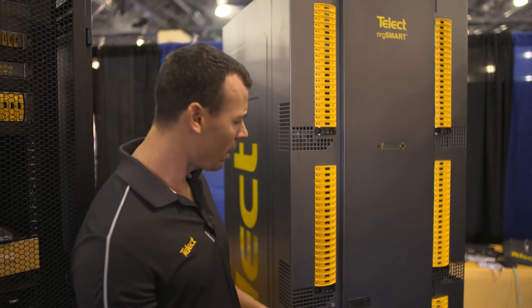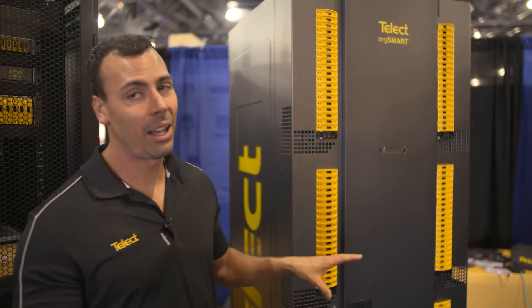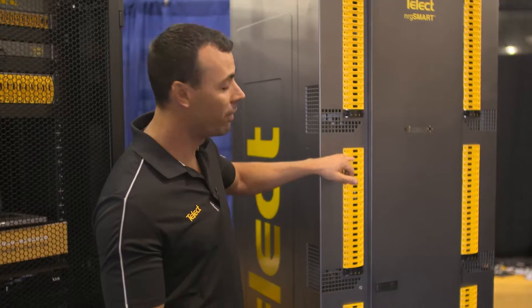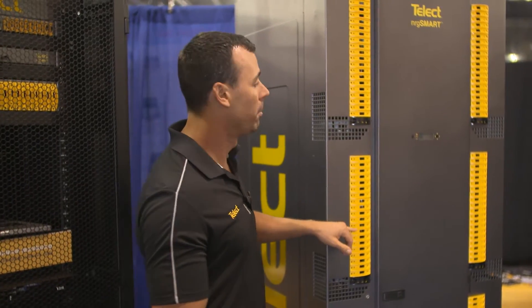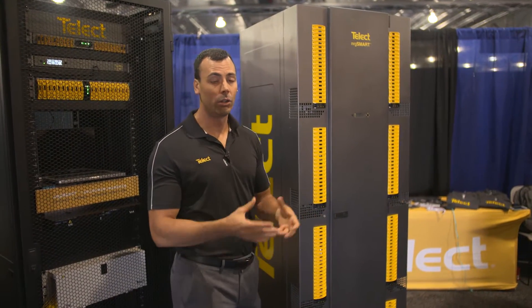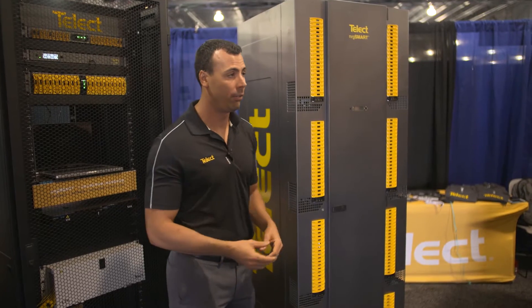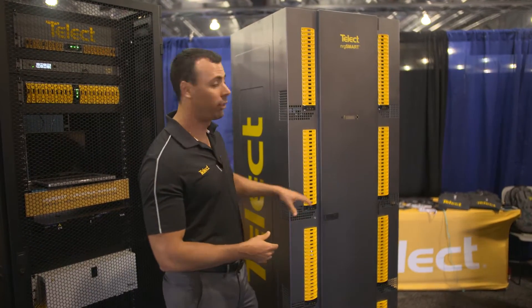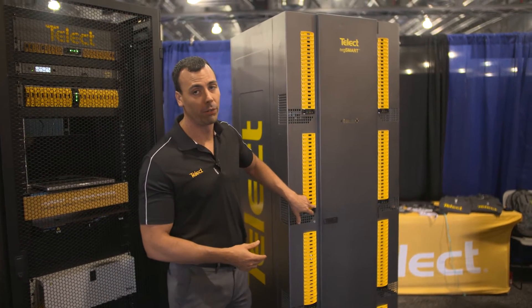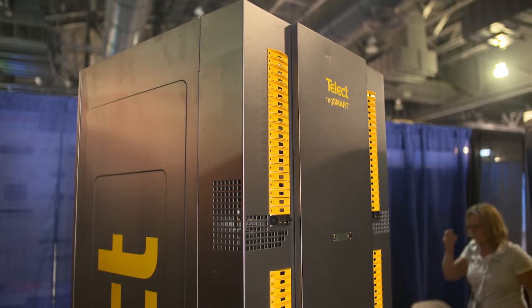EnergySmart is our circuit-level monitoring solution. Specifically, this is an 8000-amp BDFB — 1000 amps per panel. Every single breaker position we can monitor your current output, versus what most solutions these days monitor: current in, using a shunt or some other type of CT sensor. EnergySmart has a proprietary technology which measures the current at the breaker fuse position.